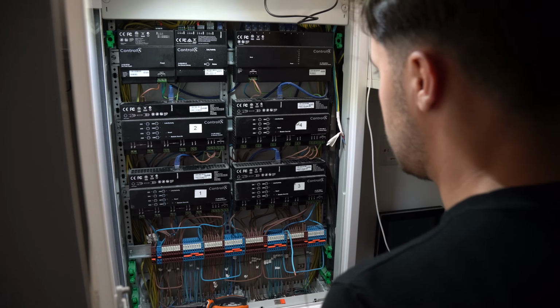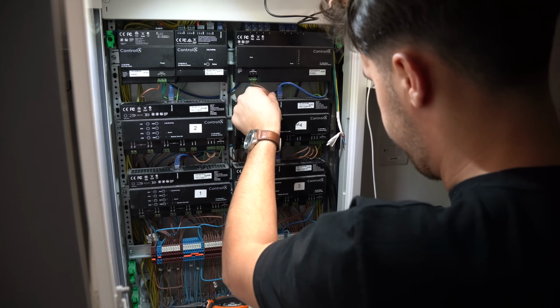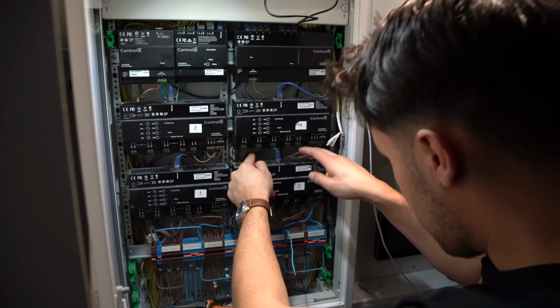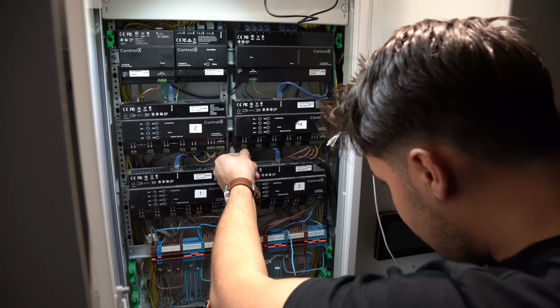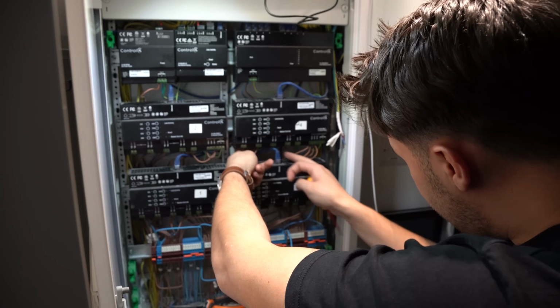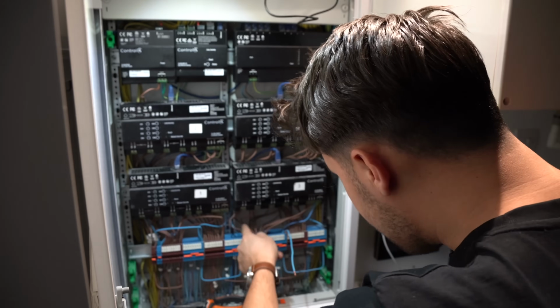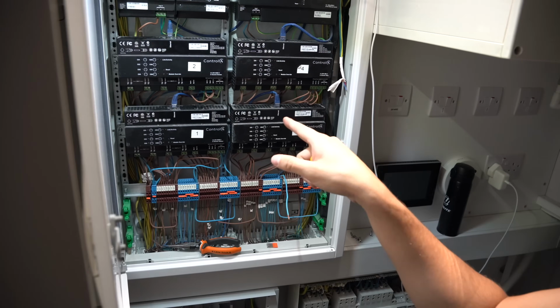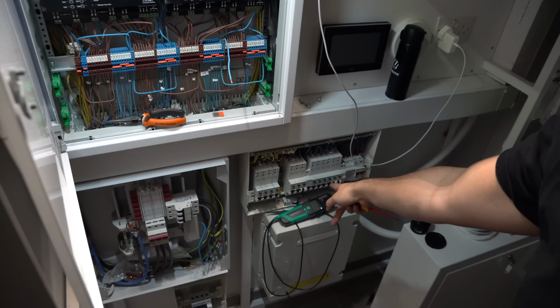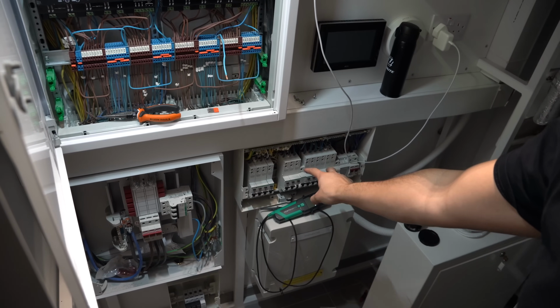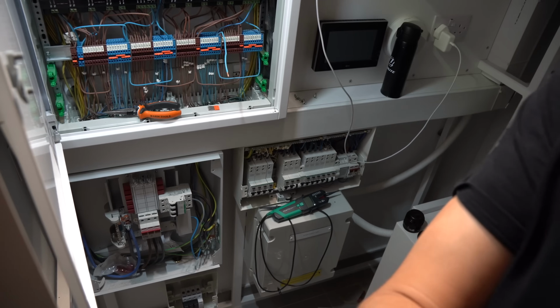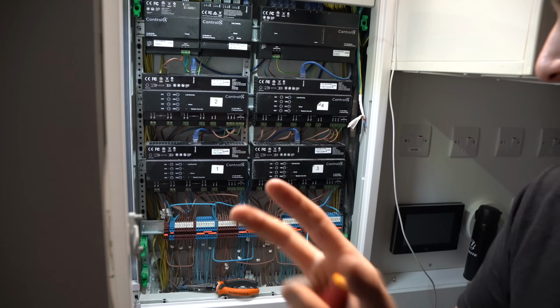We wanna make sure then we separate the lives properly, the line conductors. We just wanna make sure everything that's coming out of here is going to this half. I think it is. I'm gonna get those single cables down now into that board down there. I'm gonna fit the RCBO and just see what happens. If I get a nuisance trip, then I know that I've got a shared or a borrowed neutral somewhere.